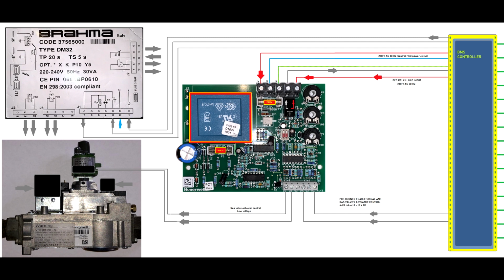I wonder if you can see the relay on the right hand side. It's painted with black. You can see the red arrow inside the relay where the electrical signal stops, because the relay is not activated by the printed circuit board, so it's not going further. To go further, this relay has to be enabled, and the printed circuit board, as I said, will only enable that relay if on the lower right hand side you have this 0 to 10 volts or 4 to 20 milliamps signal active. Don't forget when I told you about this potentiometer, you decide the value and it will start.